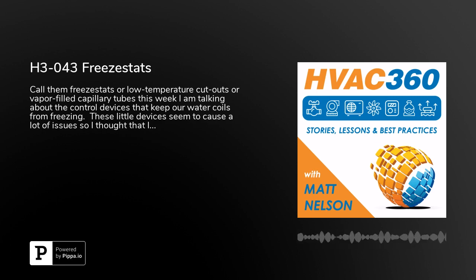So if you had 20 linear feet of this sensing element, you can cover about 20 square feet of coil. Now, for 20 square feet of coil, you do the engineer's average of, okay, say you had a standard face velocity of 500 feet per minute. You come up to a quick number of 10,000 CFM for an entire unit for one Freezestat. Now, that's important because you've got to think about the layout of these things, because you can end up with multiple Freezestats on a single unit. I've seen units that were so big that they were actually served by like 5 Freezestats.